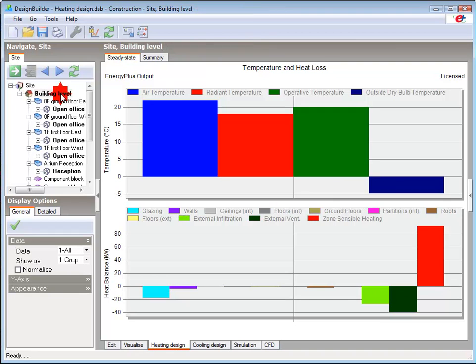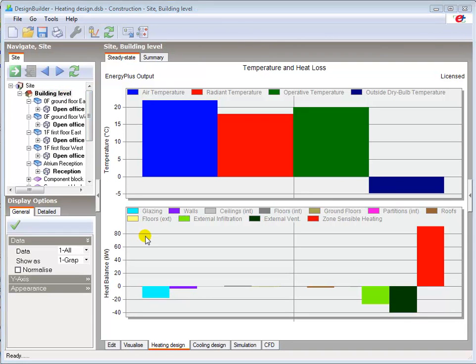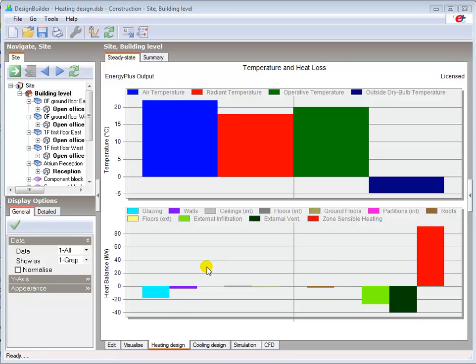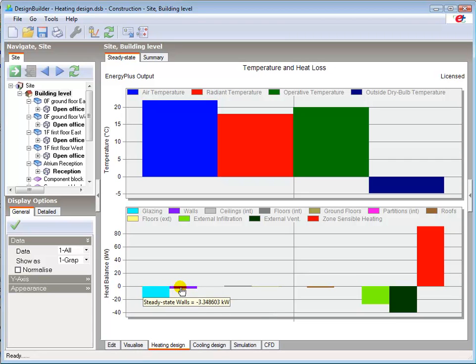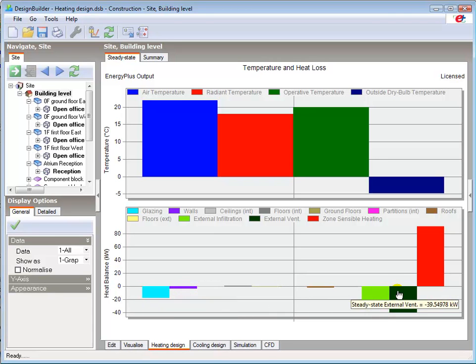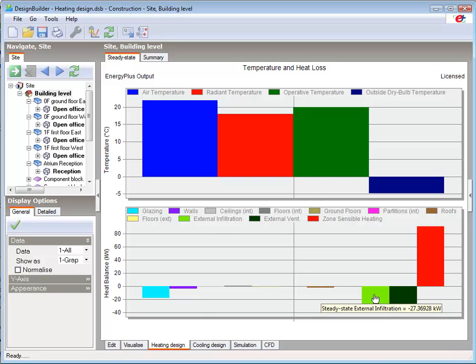Going back to building level, the heat balance graph provides a breakdown of the heat gains and losses in kilowatts for the whole building. To the left we have the heat losses totaled for each of the fabric components such as glazing at 17.86 kilowatts and walls at 3.35 kilowatts, and the infiltration and ventilation losses at 27.37 and 39.55 kilowatts respectively.